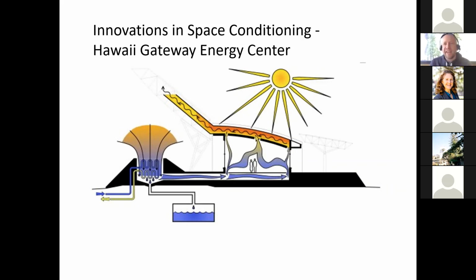There are no fans at all to move air in this building, but it has that large roof shape that absorbs solar energy and heats air, and it uses the buoyancy of the air that gets hot. That buoyant air wants to drive up, sort of get pulled up, and that's actually going to pull outside air over a cooling coil and then into the space. So it's a displacement type system, but rather than pushing air out of the floor, it's sucking it out of the ceiling and pulling air up through the floor.